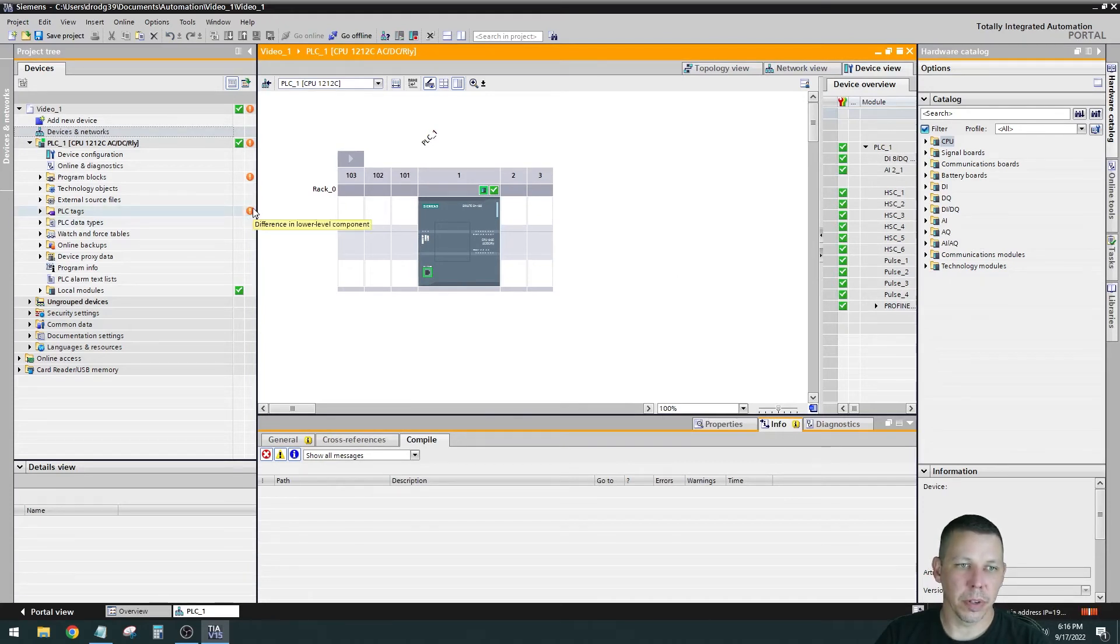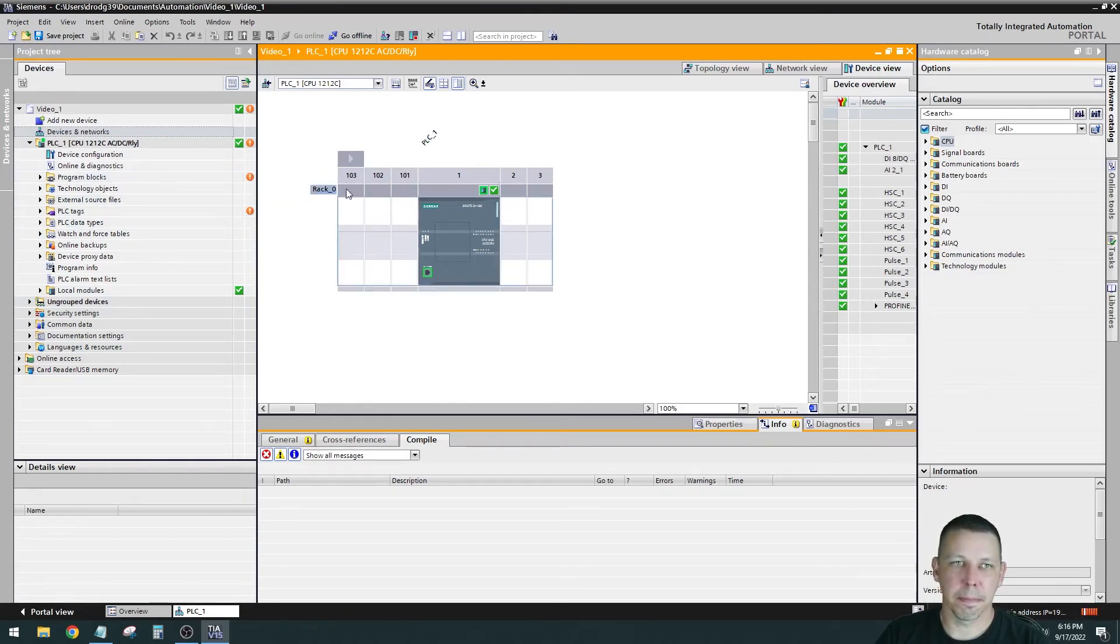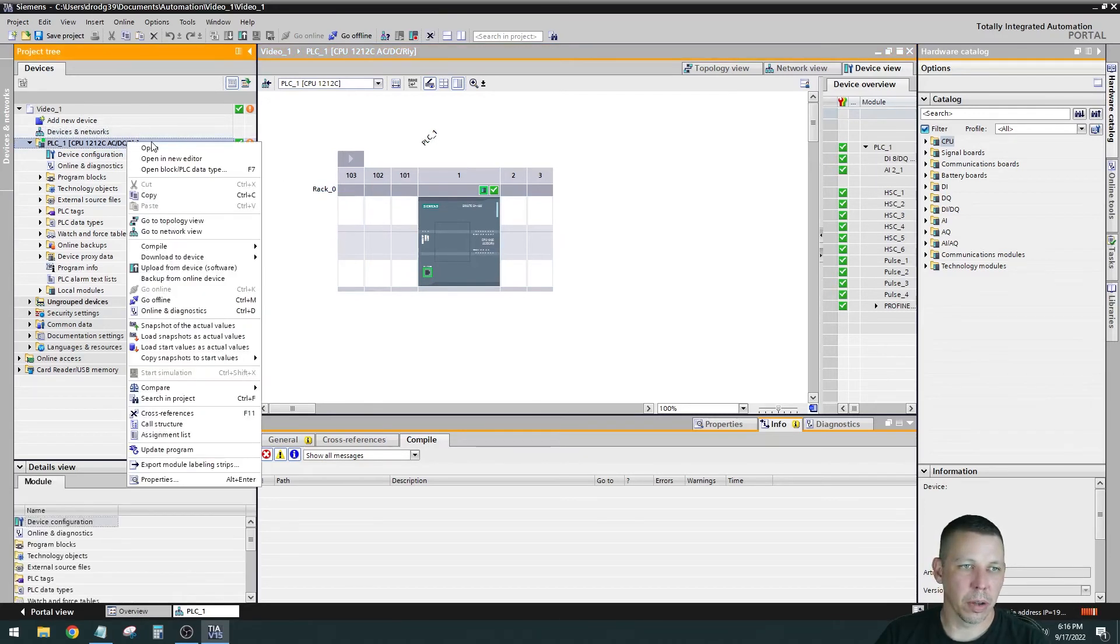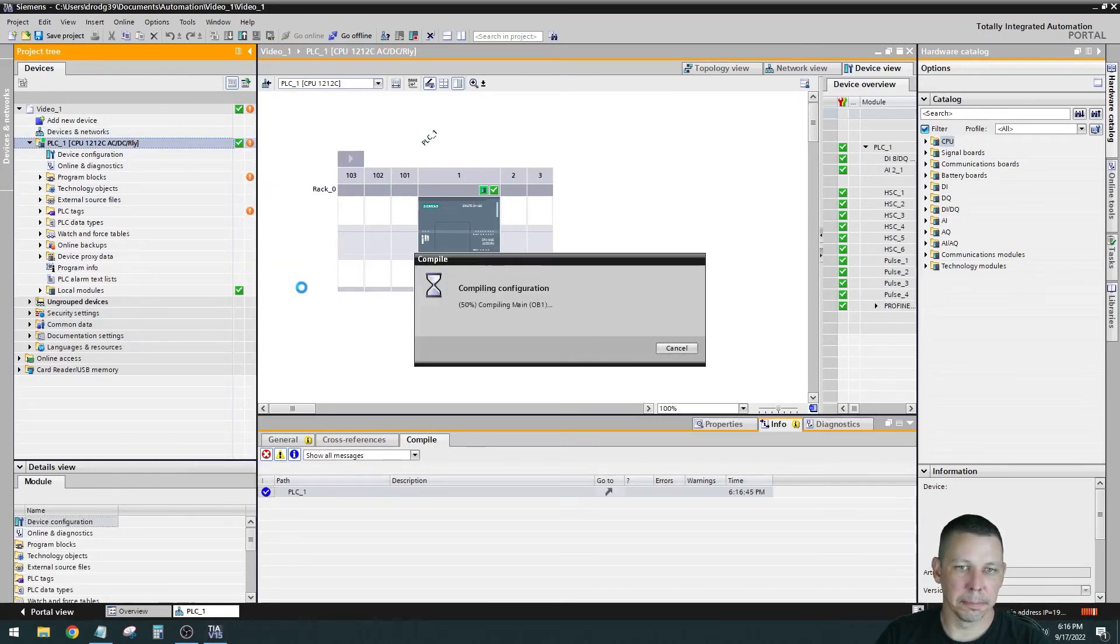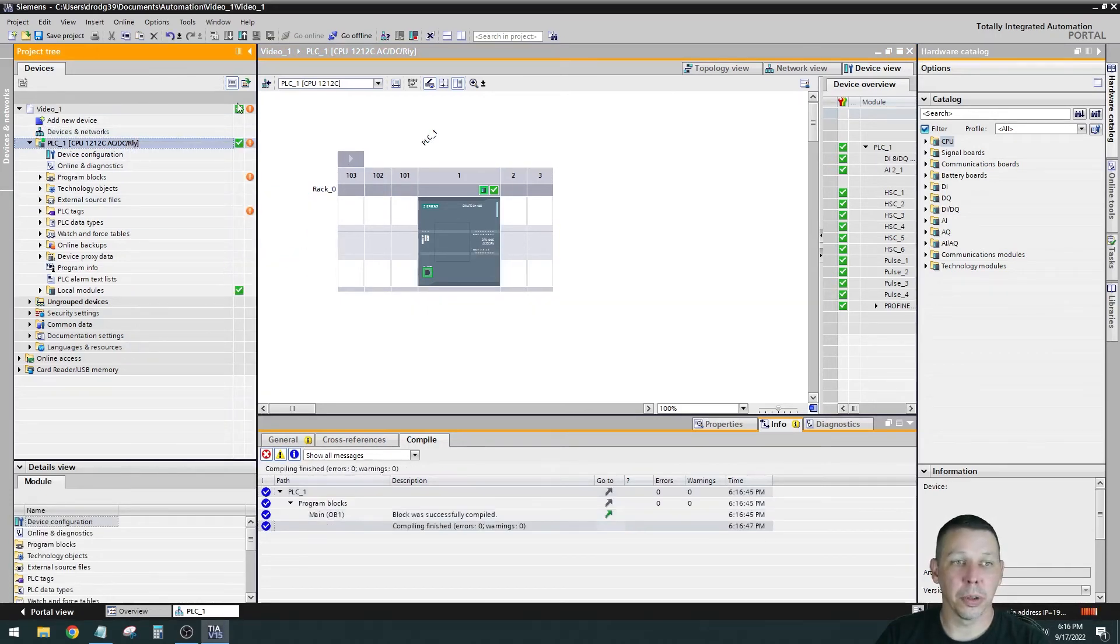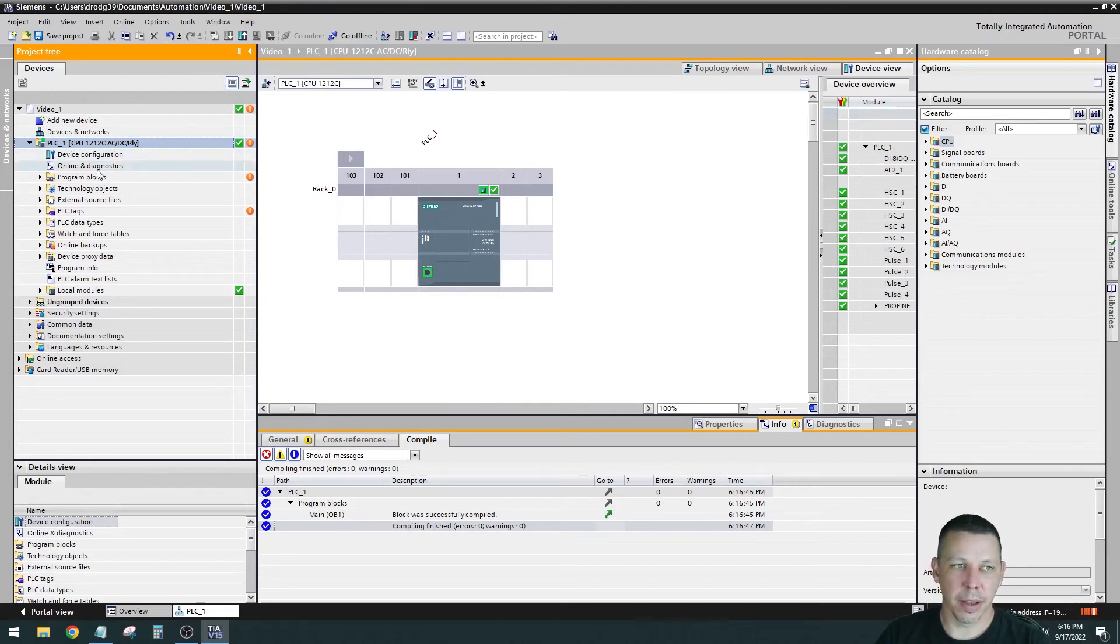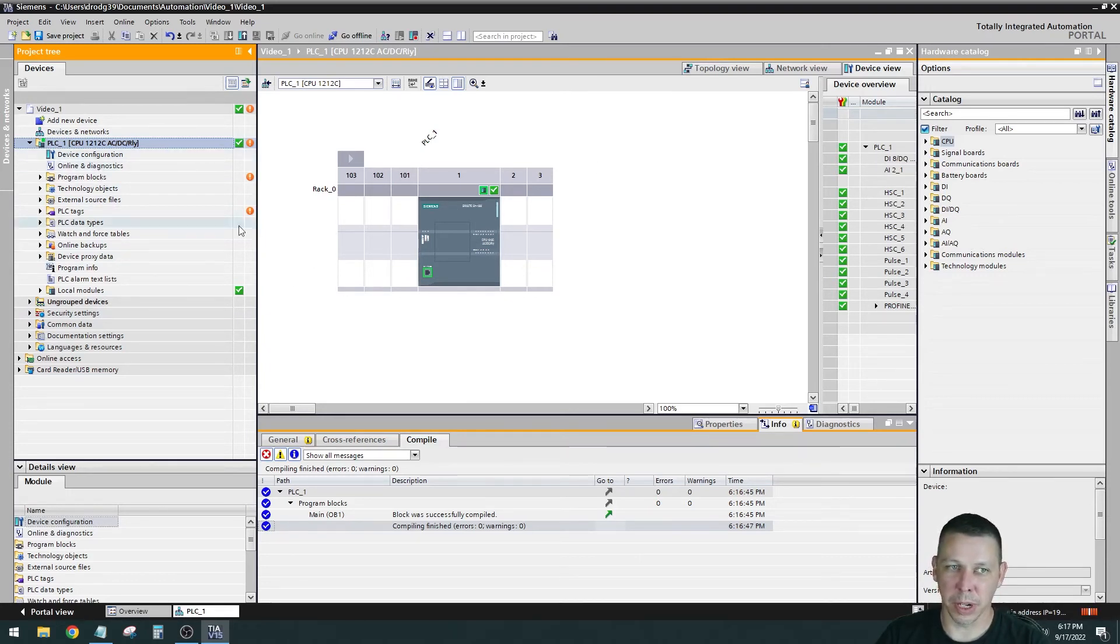These orange over here are not good. It means there's something not the same with what we're looking at in the software versus what's on the processor. So what we're going to do is right click on the processor, hit compile. I'm going to rebuild all. What we're trying to do is get all green over here. I have a blank program right now because I just opened a new project. I have no logic whatsoever in this and the processor I'm connecting to probably has logic in it. So it's not the same. That's why I'm getting these exclamation points.